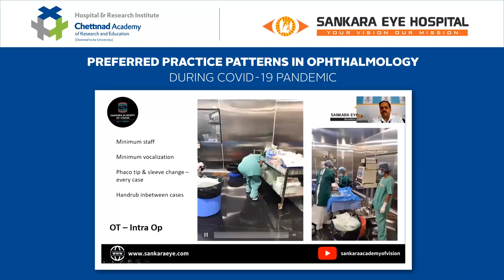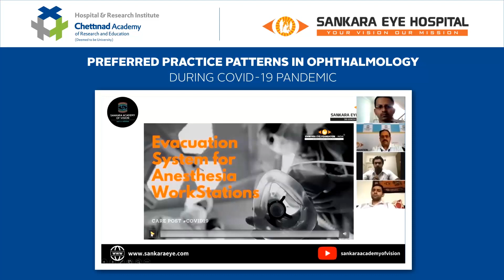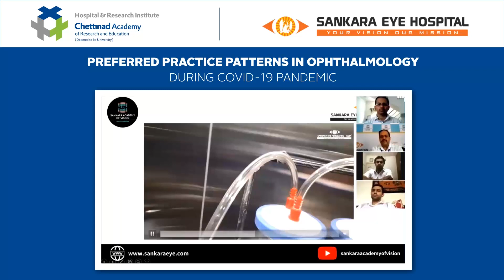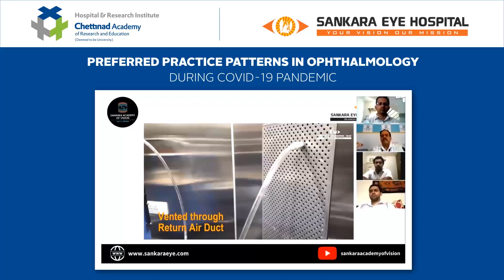This video is again a small innovation that a biomedical team came up with. So the anesthesia workstation has a small outlet where gases get expired. We've tried to collect it using the regular suction apparatus. So what we've done is we've used the regular reducers that are available with the anesthesia machine and connected them to the suction bottle where we filled 1% hypochlorite. And the second bottle, we let the run off to the return duct. The suction machine is kept off. So we're just using the two chambers of the suction apparatus. This usually is available in every operation theatre of ours. This reduces any contamination of the ambient air. So the anesthetists and the team that are handling the GAs feel that much more safe.